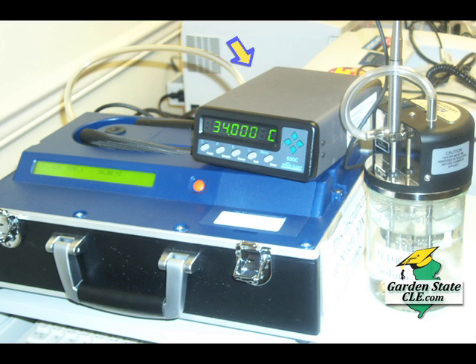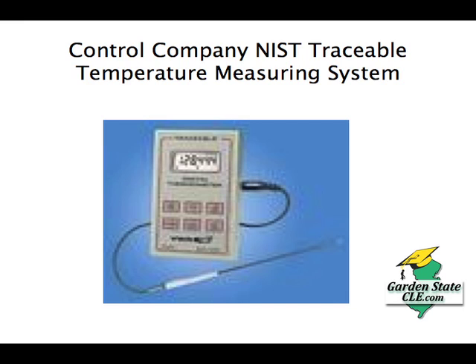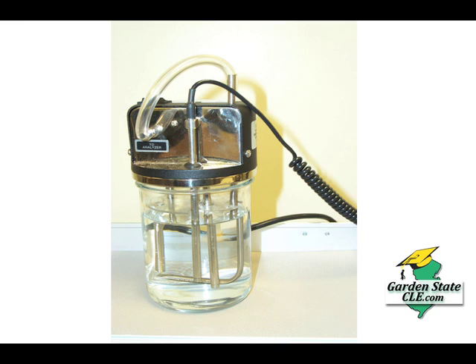The temperature probe I have is not an Alcotest temperature probe. It can hold up against the one from the control company thermometer. It's an electronic temperature probe. So when you're checking the probe value, that's something that plugs into the back of the Alcotest and then goes into here to measure the temperature. The simulator solution goes into this vessel. There's a stirring paddle here. And this is a heater, and it heats it to 34 degrees C, plus or minus. And by the way, in your materials, the plus or minus 2% range is wrong. It needs to be within a tighter tolerance than what's shown.